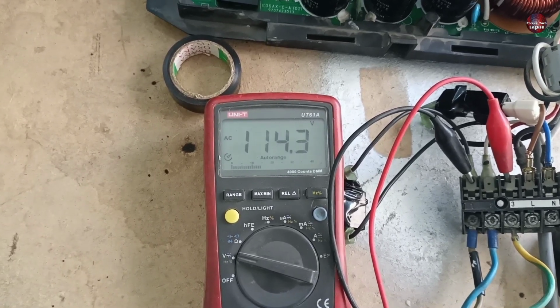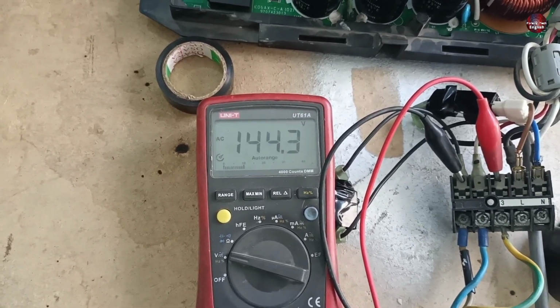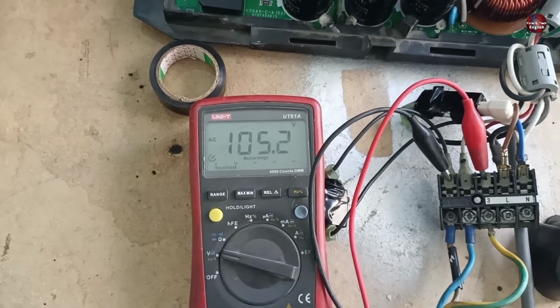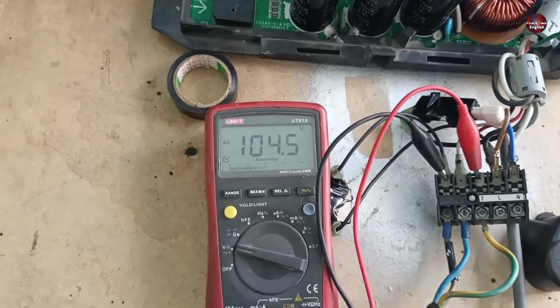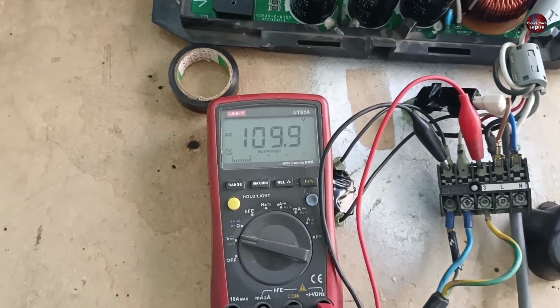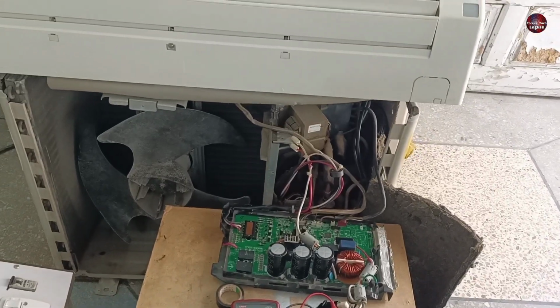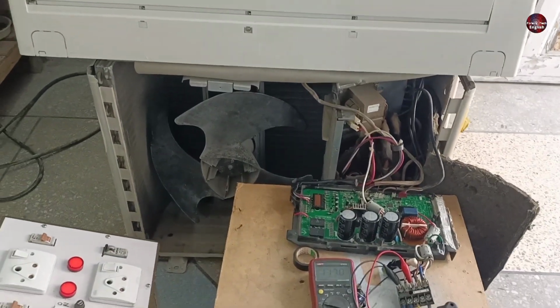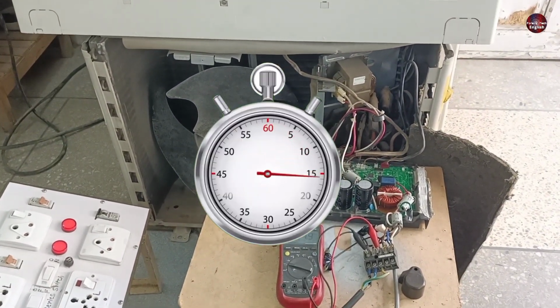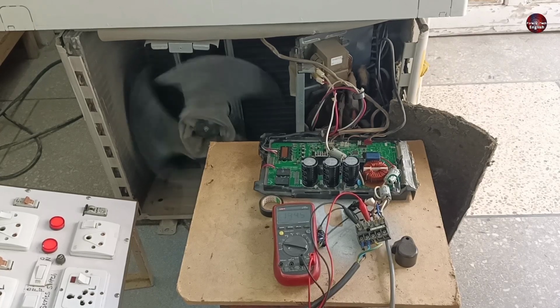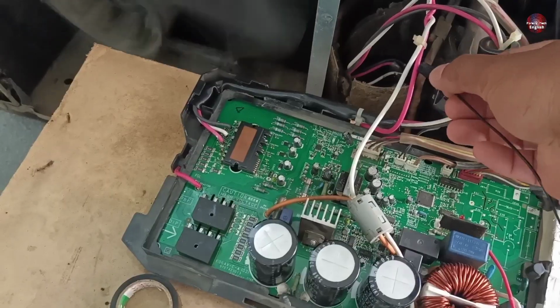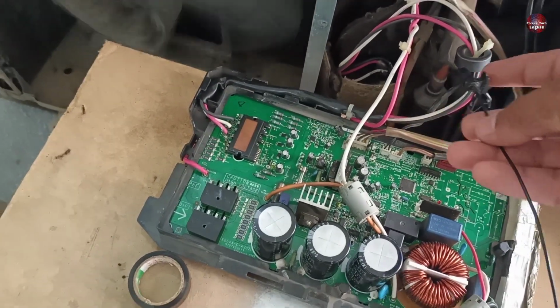As I check the communication on the multimeter, the voltages fluctuate the same as before. We can't tell what signal the indoor and outdoor are exchanging, but through the fluctuation of the voltages we know both motherboards are communicating fine. Now I will wait for the outdoor unit to start. The outdoor fan motor has started working, and the compressor has also started to work.